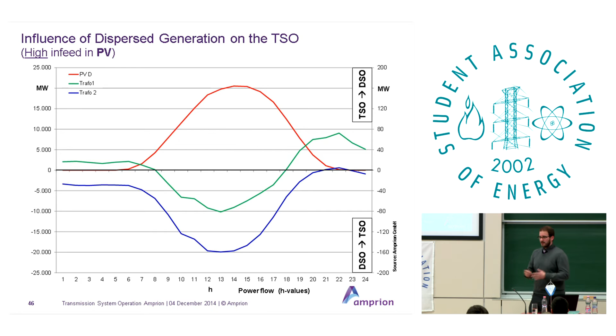But there's a reason I've shown DSO to TSO flow as well. Take another example: a day with high PV infeed, over 20,000 megawatts of PV generation. Now we see a power flow from DSO to TSO grid—so much generation in the DSO grid that it can't be handled locally, so it's pushed back up to the TSO. This change in load flow direction is a genuinely new situation everyone has to deal with and find solutions for. It's not simply going left instead of right—it's something fundamentally different.